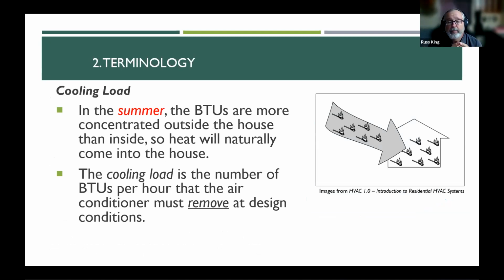All right. Another important term is load. What is the load on the house? We have a cooling load and a heating load. The cooling load is in the summer; it's the number of BTUs coming into the house. Where are those BTUs coming from? They're coming from the outside. You've got a certain number of BTUs in the house and it's hotter outside, so there are more BTUs outside than inside. The BTUs outside are more dense, let's say, and they're coming into the house. You can estimate that if you know the indoor temperature, the outdoor temperature, and the properties of the various surfaces: the areas of the walls, how much insulation is in them, what kind of windows you have, and how leaky the house is. You can calculate how many BTUs are coming into the house on a hot day.